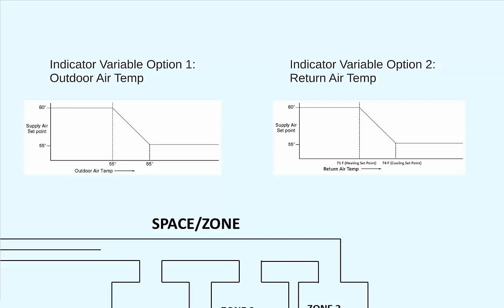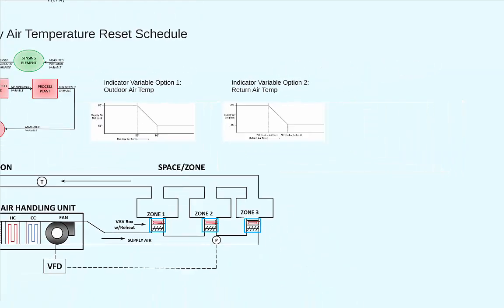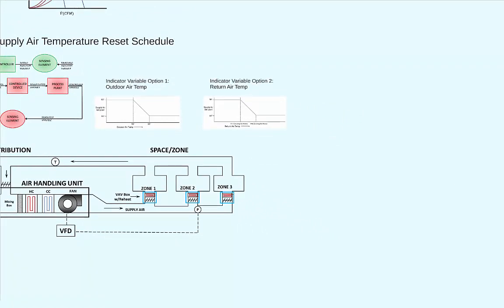Now, you might be wondering why we're not more aggressive with this supply air temperature reset schedule. If a return air temperature of 71 is an indication the majority of the building is in heating mode, why not bring the supply air temperature up to 65 or maybe even 70 degrees Fahrenheit? That would prevent reheating of the air further down the duct path in the VAV boxes. Well, for one, oftentimes the air coming out of the air handling unit is going to be around that temperature anyways.